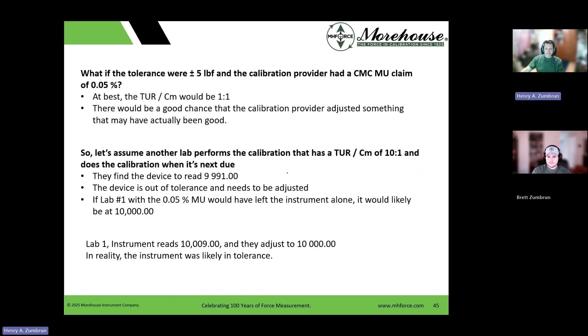basically the chances of anything happening are very low, and they can say the device is still in tolerance. So you calibrate lab 1. You use this to calibrate other instruments. Reference standard loaded to 10,000 when it's actually 9991.